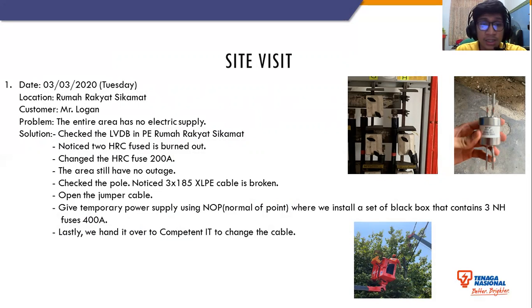We changed the HRC fuse to 200 amp. We changed the HRC fuse to 100 amp. The area still had no supply, so we checked the pole. We noticed that the 3 times 185 XLPE cable is broken. We opened the jumper cable. We gave temporary supply using NOP, that is normal open point, which I will explain later, where we installed a set of black box that contains 3 NH fuses for 400 amp. Lastly, we handed it over to a competent person to change the cable.